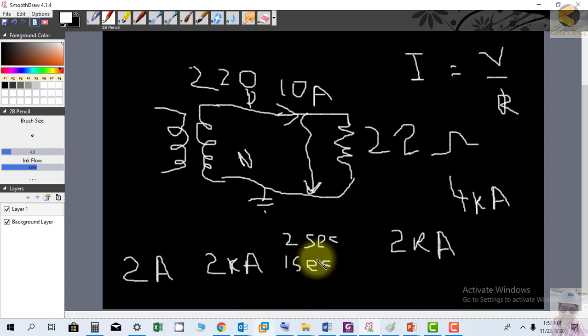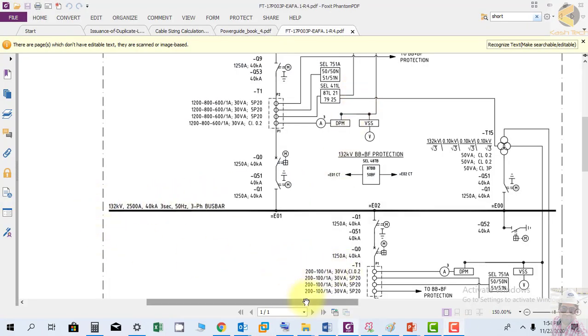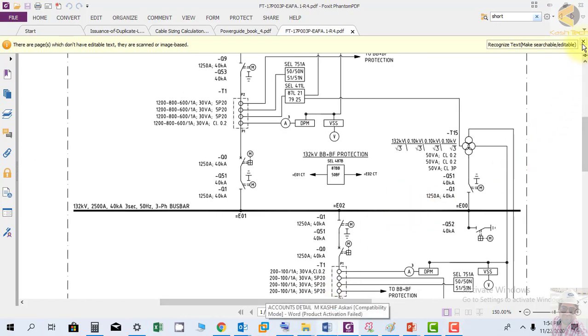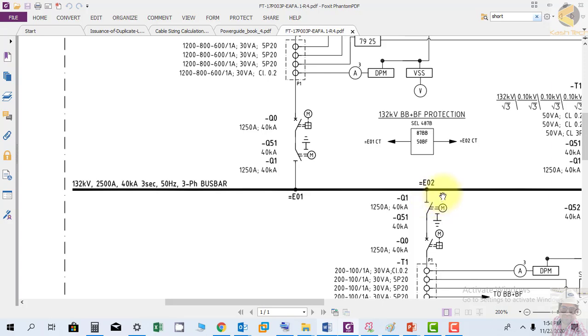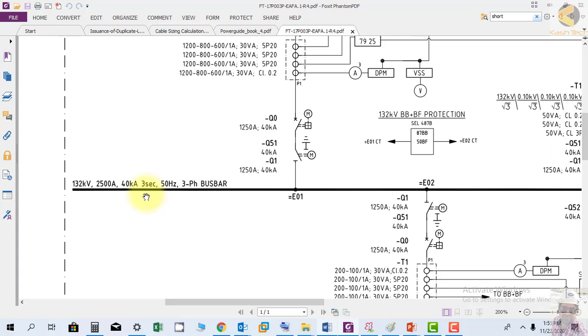Looking at a single line diagram example of a 132kV substation: the black bus bar is feeding power in and out. The rating of this bus bar is 132kV voltage level and 2500 amperes continuous rating — the bus bar will not overheat beyond its limit at this continuous current. The short circuit rating is also mentioned: 40 kiloamperes for 3 seconds.